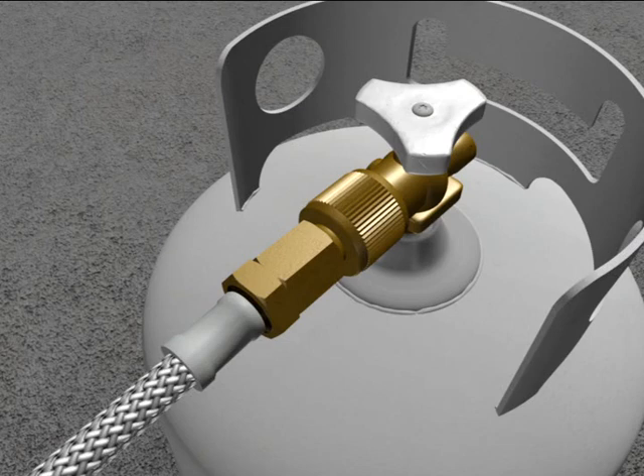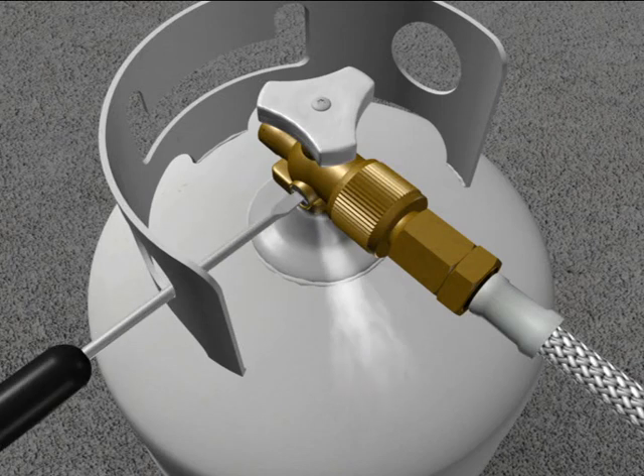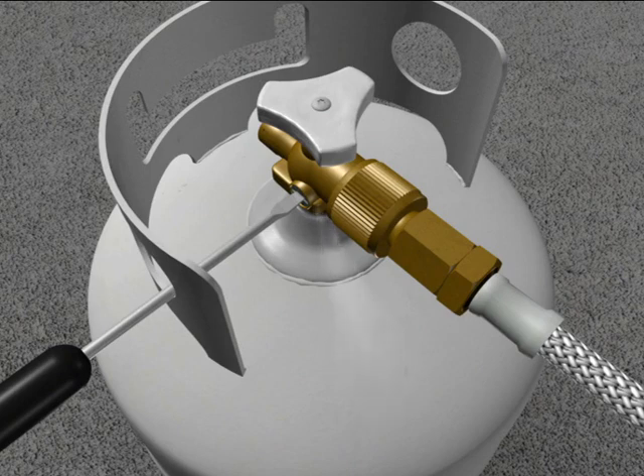On the receiving cylinder, open the cylinder valve and the fixed ullage bleed valve about two turns. You'll hear the gas and some liquid hissing out of this valve.